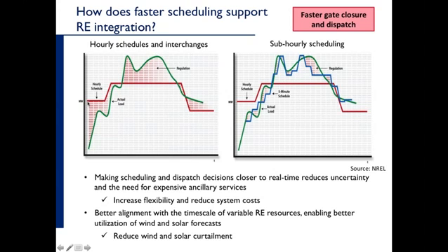And now what we want to do is take a look at the hourly schedule, or the hourly economic dispatch. And typically the dispatch is done based on the average demand or the average net demand through the hour. And so you can see that here. It's hard to tell exactly what this average is, but roughly for this hour you can see the average is right in here, and you have a flat dispatch block. This whole big red flat block is 1 hour. When the next hour begins, we can ramp our generation so that they're at their new dispatch point, and they're going to remain at that dispatch point for the next hour.